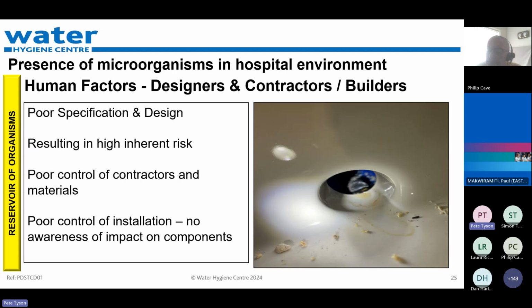This could be from a designers, contractors and builders perspective, resulting in poor specification and design, high inherent risk, poor control of contractors and materials, poor control of installation, no awareness of impact on components, and clinical wash basins used as urinals during construction, for example. Components that have not been kept sealed and covered, domestic hot water returns not installed to the specification detailed. A recent example of a new build with 150 outlets, none were installed to the specified 300 millimeters.